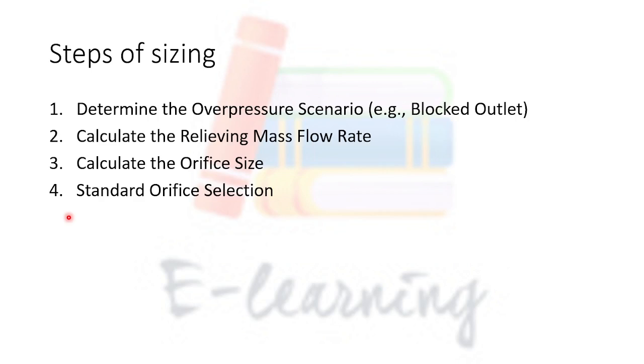In today's short video tutorial we are going to discuss the process of sizing a pressure safety valve. These are the four main steps of sizing a PSV. In the first step we determine the overpressure scenario on which we design the PSV. Then we calculate the relieving mass flow rate. The third step is the calculation of orifice size, and after that we select the standard orifice for the PSV.